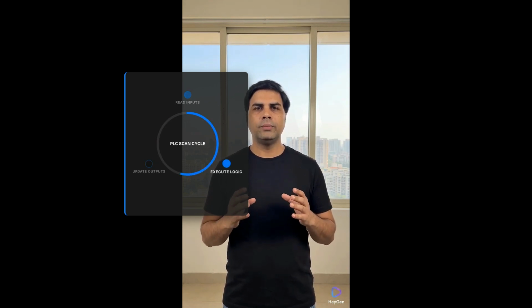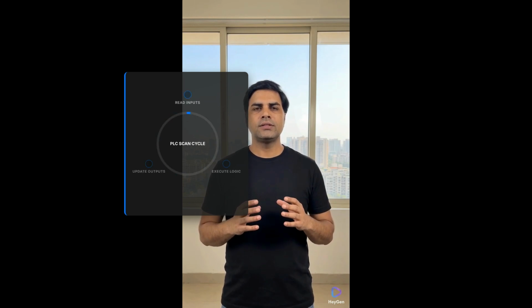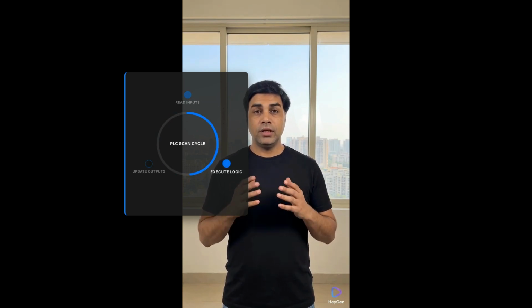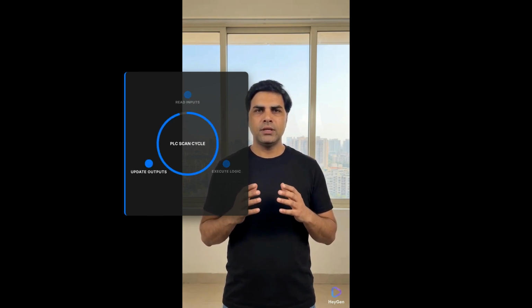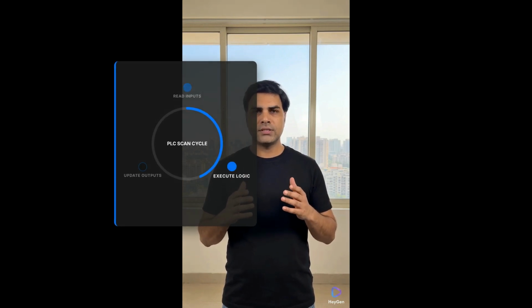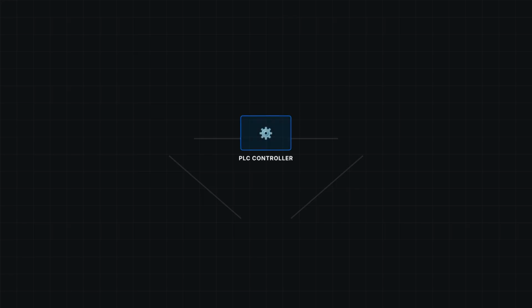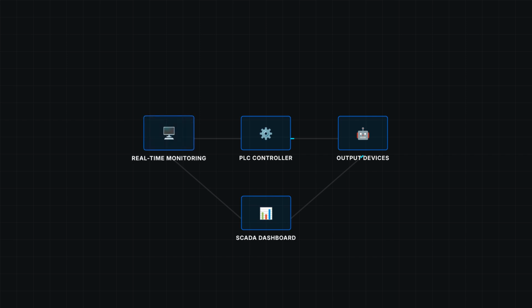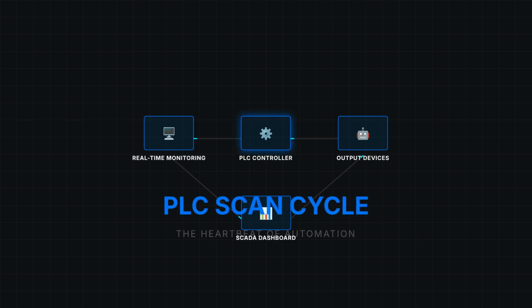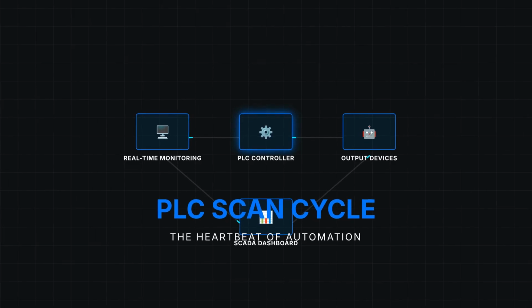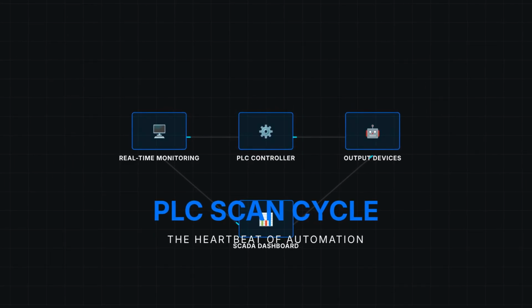Now let's follow the complete journey of data. A sensor detects information. The information reaches the PLC. The PLC processes the logic. The PLC sends commands to output devices. The devices perform actions. Production information is sent to SCADA. Operators monitor everything in real time. This cycle repeats continuously, thousands of times every second. This is called the PLC scan cycle, and it is the heartbeat of industrial automation.